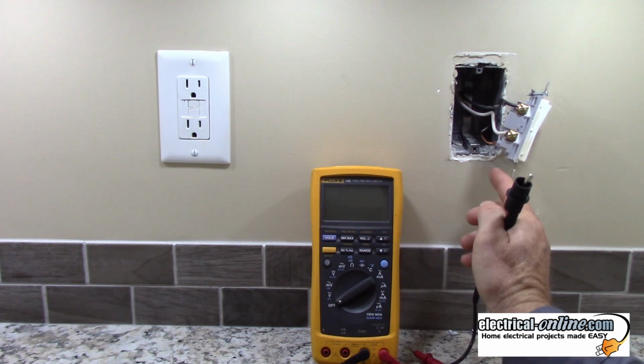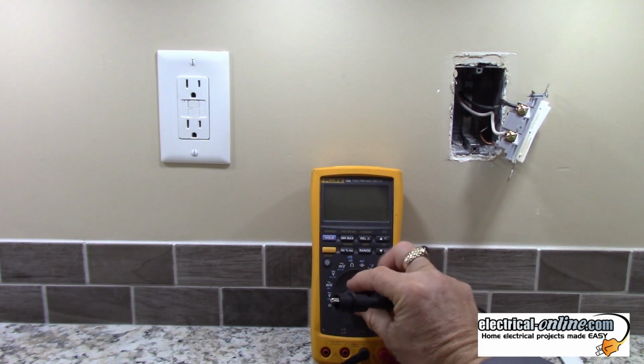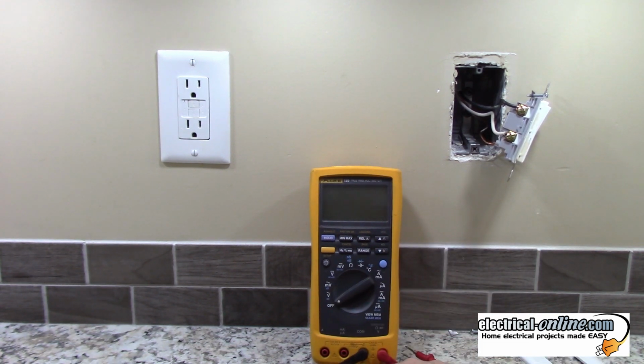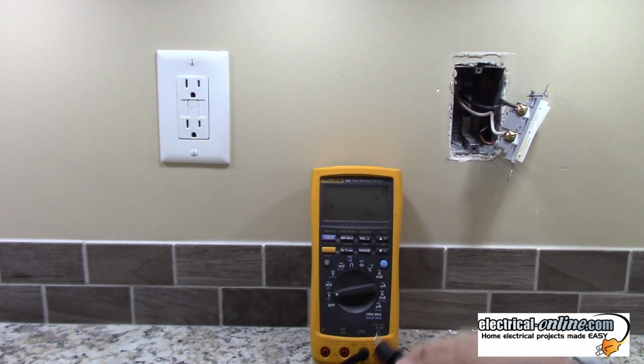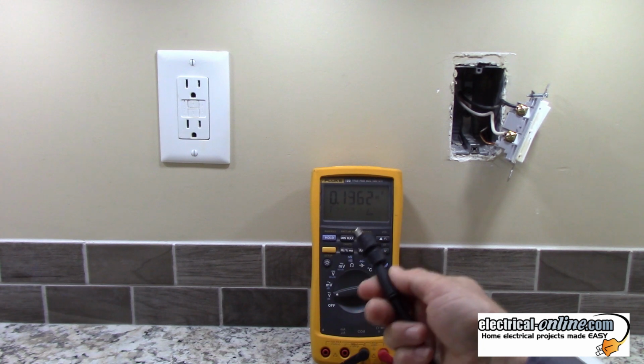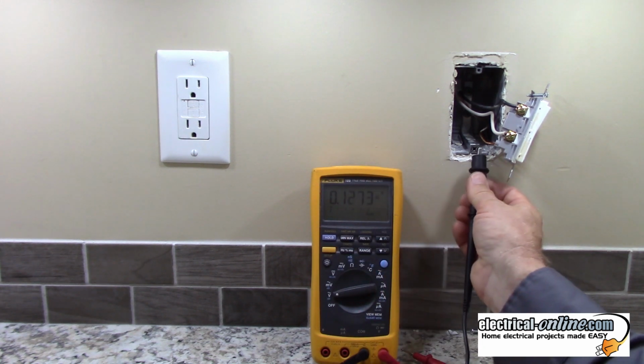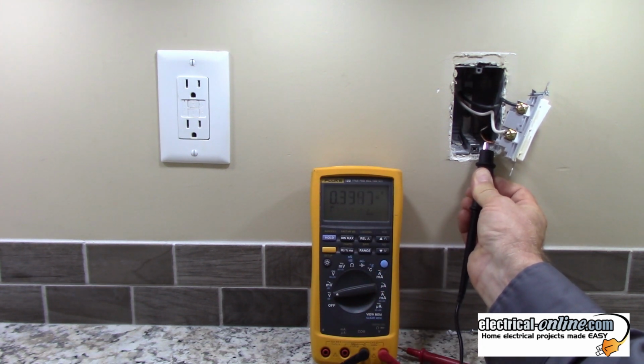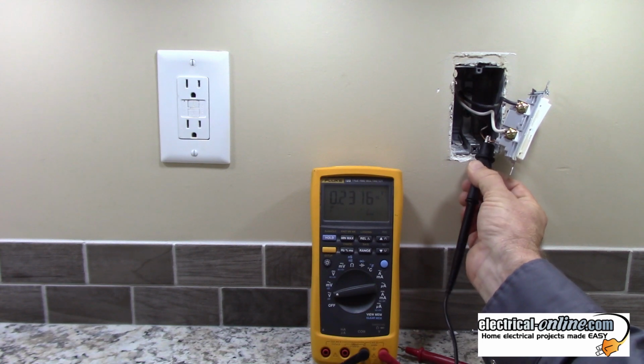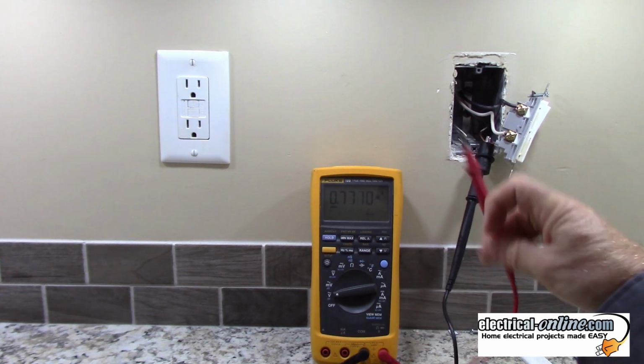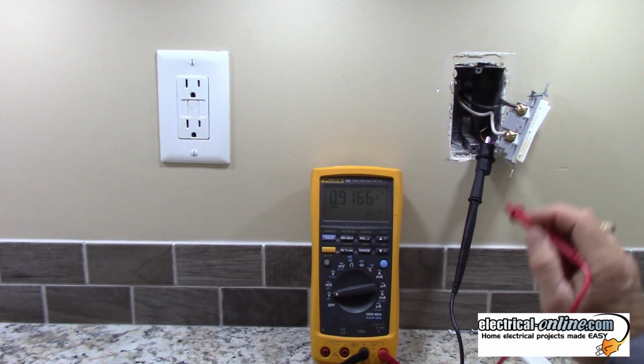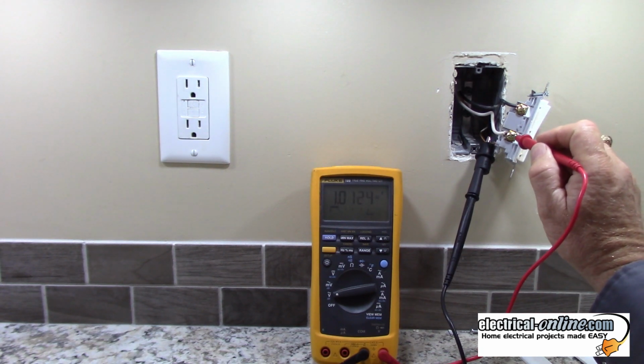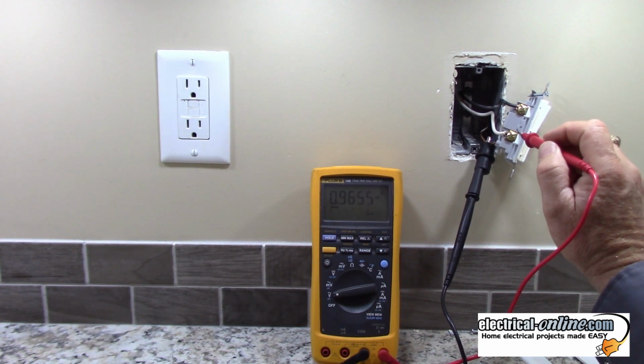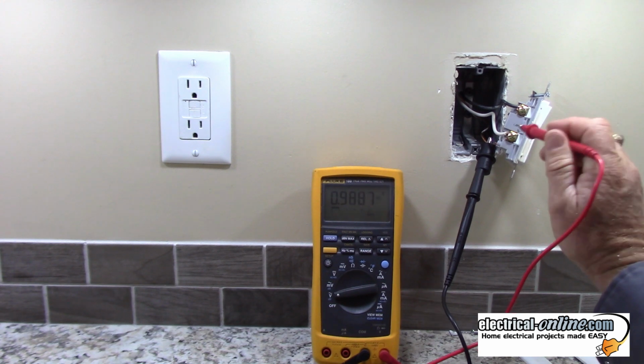So with a switch opened up like this, again, meter leads, black in common, red in the voltage probe, turn it to volts AC. Now I'm going to put an alligator clip on, and I'm going to get a good solid bite on that bare ground wire with my alligator clip. Then using my red probe, I'm going to check right at the bare wire, which is hooked to the terminal, to see if we have voltage. So let's have a look.